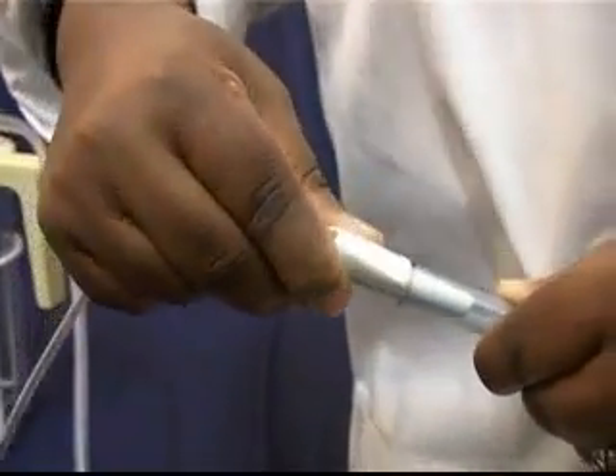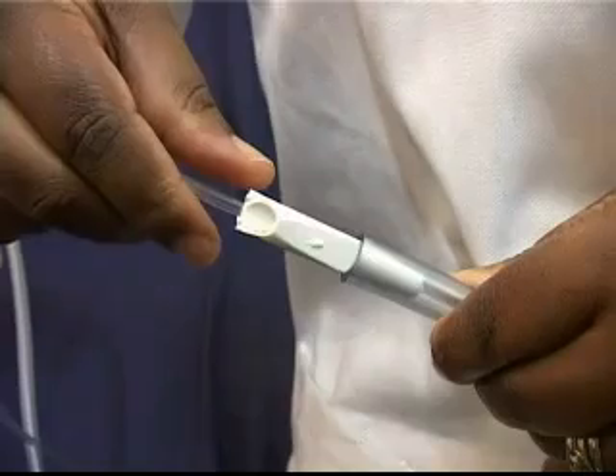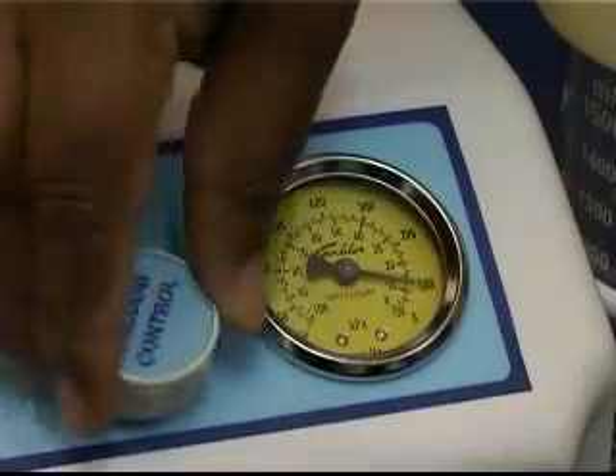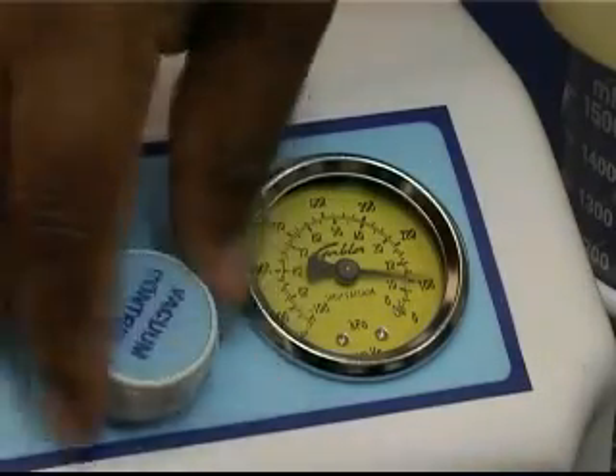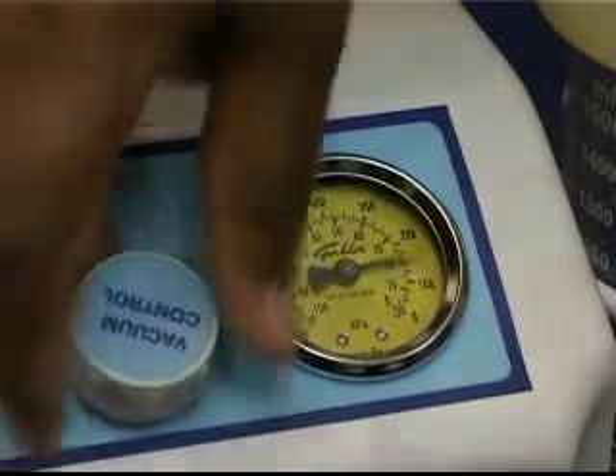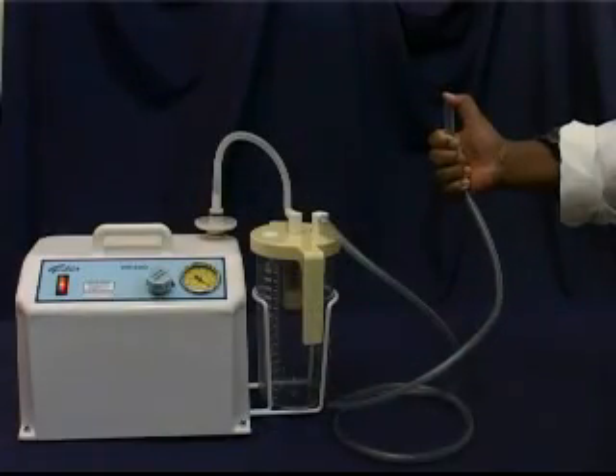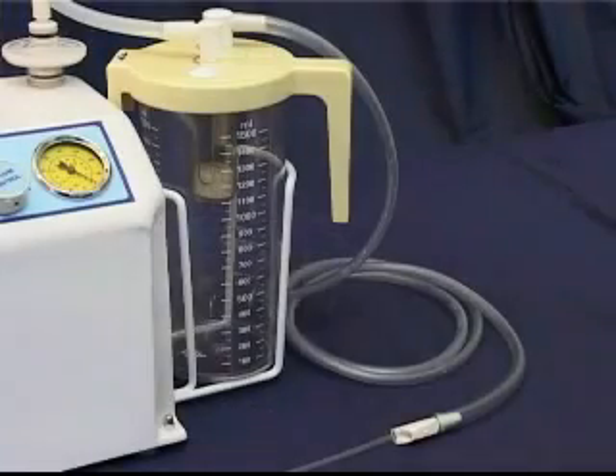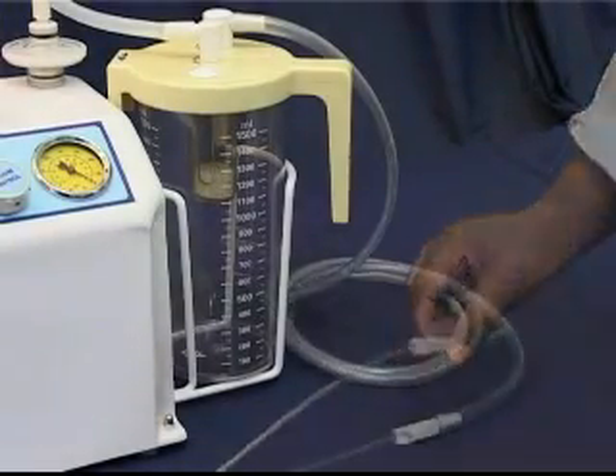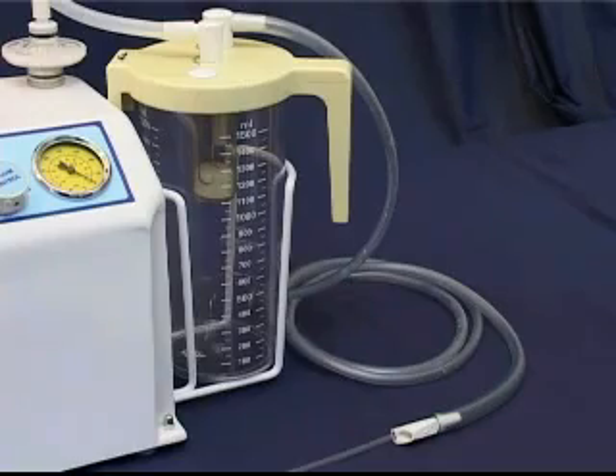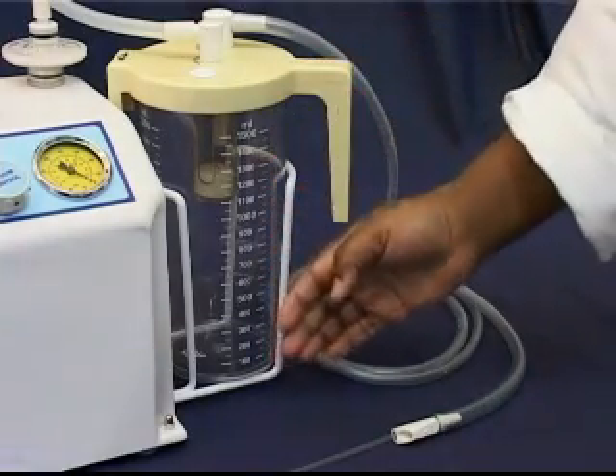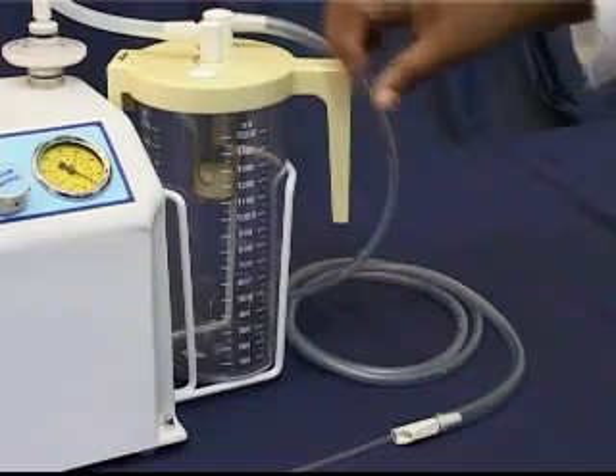Connect a suitable catheter to the end of the silicone tubing to the patient. Ensure that the correct suction pressure is chosen by turning the control knob while blocking the tube to the patient. The suction pump is now ready for use. An anti-foam agent may be put into the fluid collection jar before use to prevent the possibility of frothing.